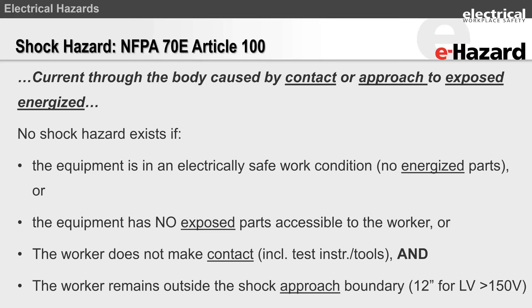Or if the equipment has no exposed parts. Exposed means where you can unintentionally make contact with your body, a tool, an instrument. Okay, that is what exposed means. The worker does not make contact through any of those test instruments, and the worker remains more than 12 inches away for low voltage applications, 150 volts up to 751 volts. It is 12 inches away.